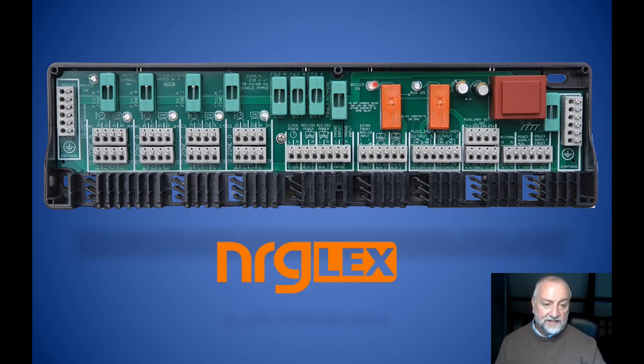There's 2 relays. The boiler relay has a double pole switch which can operate a boiler or 2 boilers. They're volt-free contacts, so you can use them for switch lives or volt-free. Each boiler has a 3 amp fuse. So boiler 1 has a live and neutral, boiler 2 live and neutral with 3 amp fusing on the lives, and there's a 3 amp control for if you want to have one common control for everything. You can feed it from here.